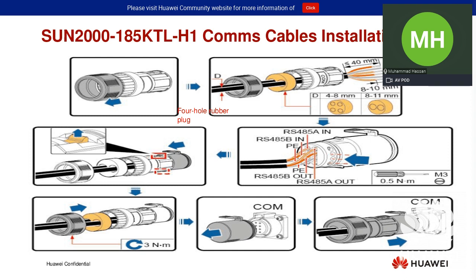Here is the procedure for installing the RS485 communication cable. Always make sure that you take out the locking nut. We are providing a 2-hole or 4-hole rubber inside the inverter box, so that you can use the appropriate hole rubber to seal the communication connectors, so that no water or insects go inside and cause any problem.